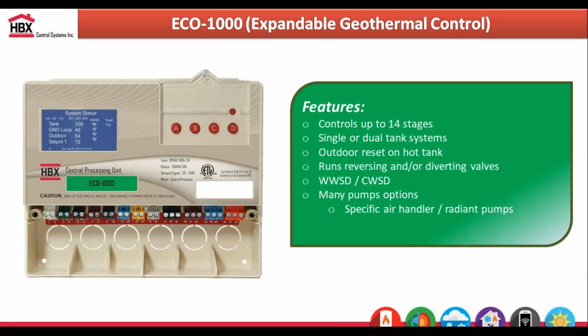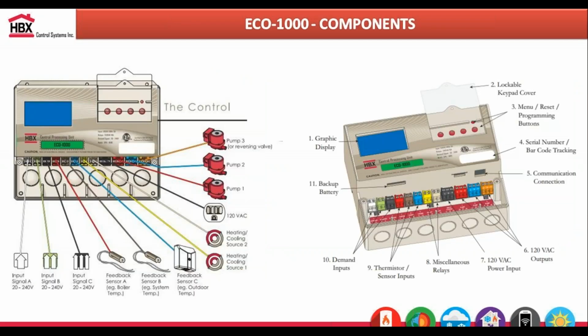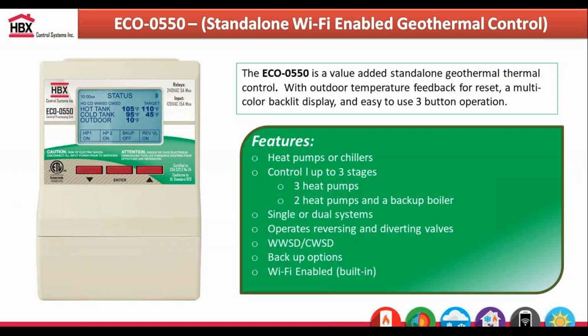Cold tank setup is just based off a manually inputted set point for the cold tank, but for the 1000 you can do outdoor reset for your cold tank, unlike the Eco 550. We can run our reversing valve or diverting valves as well on the Eco 1000, and you also have the capability to control a backup heat source with the 1000 series. We can do 2 heat pumps on the main controller itself, and then you would just add on EXP 100s to accumulate more stages if you are utilizing more than 3 stages.